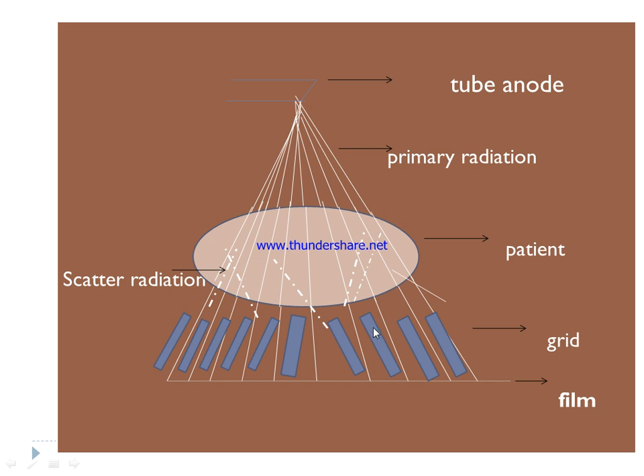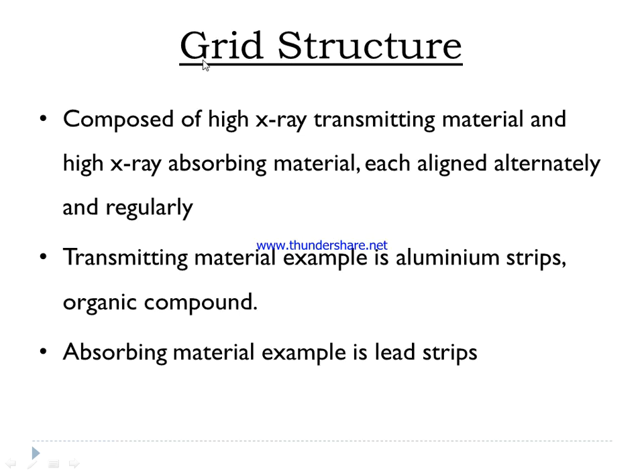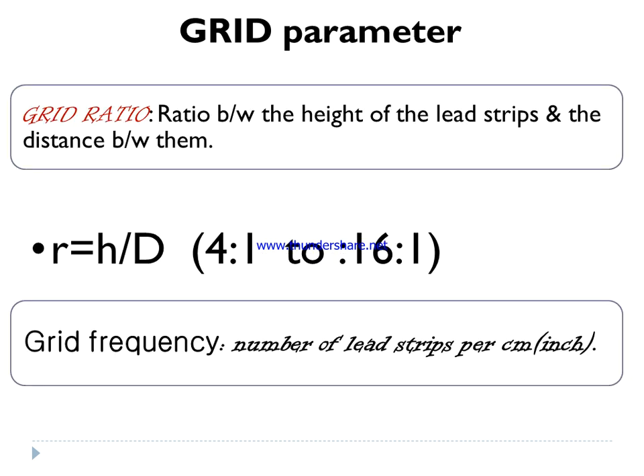Between the lead strip layers, interspace material is present — this is essentially the grid. Below the grid is the film. The patient is shown, with dotted lines representing scattered radiation and the solid line representing primary radiation from the x-ray tube. Grid structure is composed of high x-ray transmitting materials and high x-ray absorbing materials arranged alternately. Transmitting materials include aluminum strips and organic compounds; absorbing materials include lead strips.